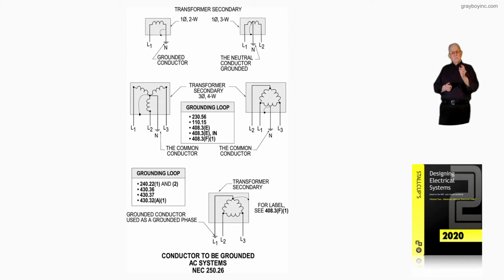250.20A1 dealt with where you would have to ground low voltage systems of less than 50 volts, or you wouldn't have to ground them. 250.20B said if you use a transformer in the manner that's listed here, you have to pull the grounded conductor to the service equipment and ground there. Basically, you're grounding the transformer.